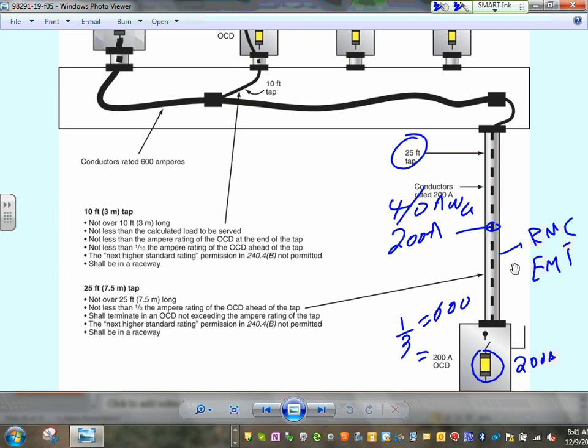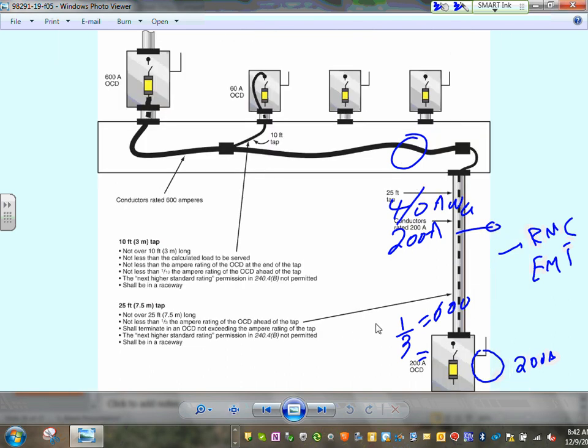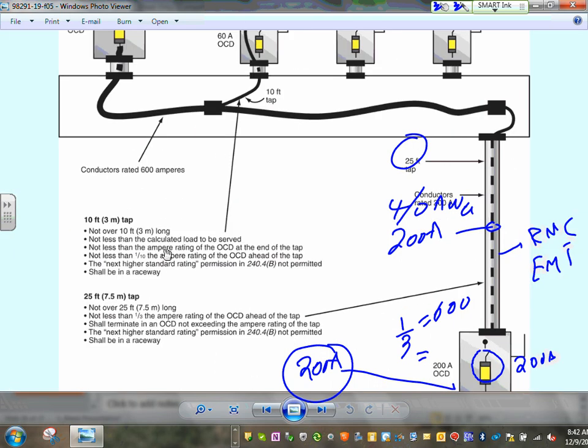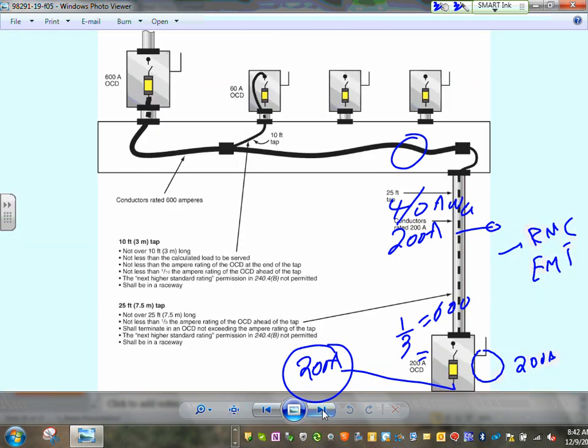Any comments, guys? Any questions about the 10-foot and the 25 feet? You will hear me talking about these in the spring, the same thing, and after that, you're on your own. There's a lot of good information, guys, in these chapters. You can handle as much as you can at this point. The load that we feed from here, when you put a load right in here, cannot exceed the 200 amp. That's the rules for the 25-foot rule. The 10-foot is exactly the same, except the multiplier is 1/10.